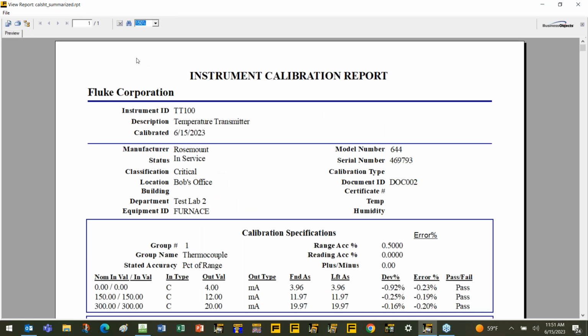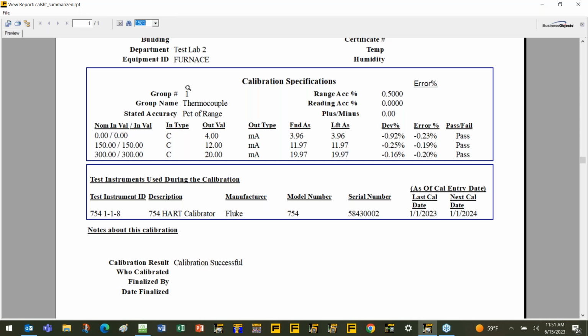it looks like. So you'll see the information about what was the instrument, company name, more information about that device from the instrument. And then here's the special part. Here's the boxes. This is where the actual data was uploaded from the 754. So you'll see in the first box, it'll show the nominal values, what the output was supposed to be. Here's what the actual as found was. Notice we didn't have to repeat the as left, so it just copied the same thing over. And then here's your error percent that was documented, and it passed.